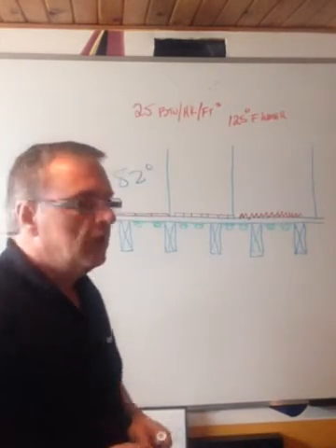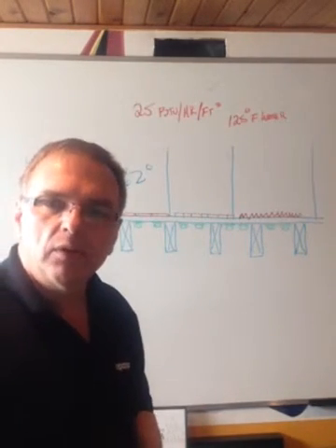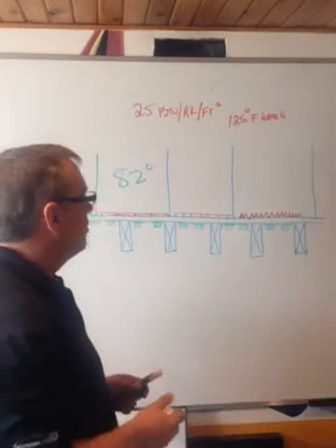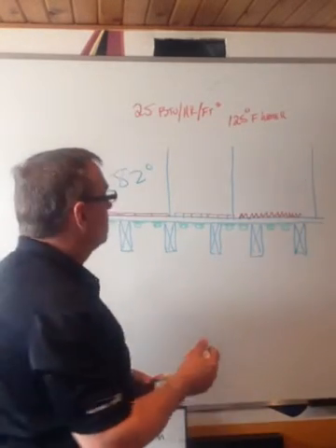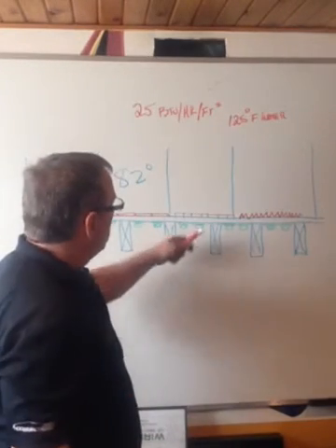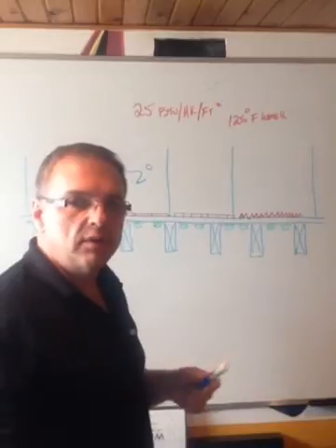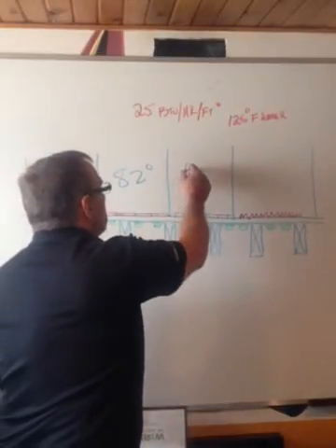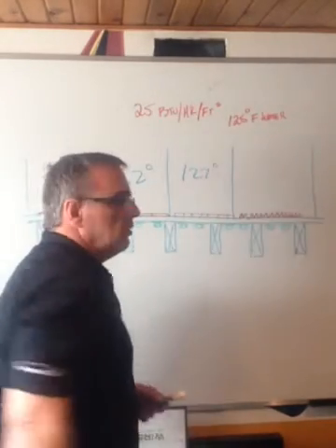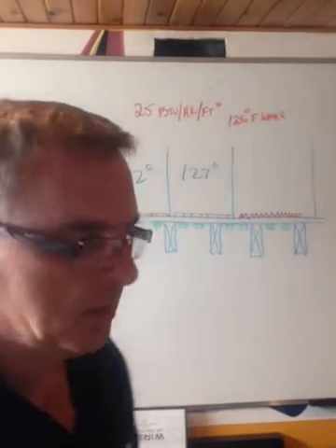Third room. Again, identical in every way other than floor covering. We're going to use hardwood. This might be the living room or a vast majority of the house. Again, you have your resistance for the subfloor. You have the resistance now of the hardwood, which is a little higher. We find out we require a water temperature of 127 degrees to heat the room now.